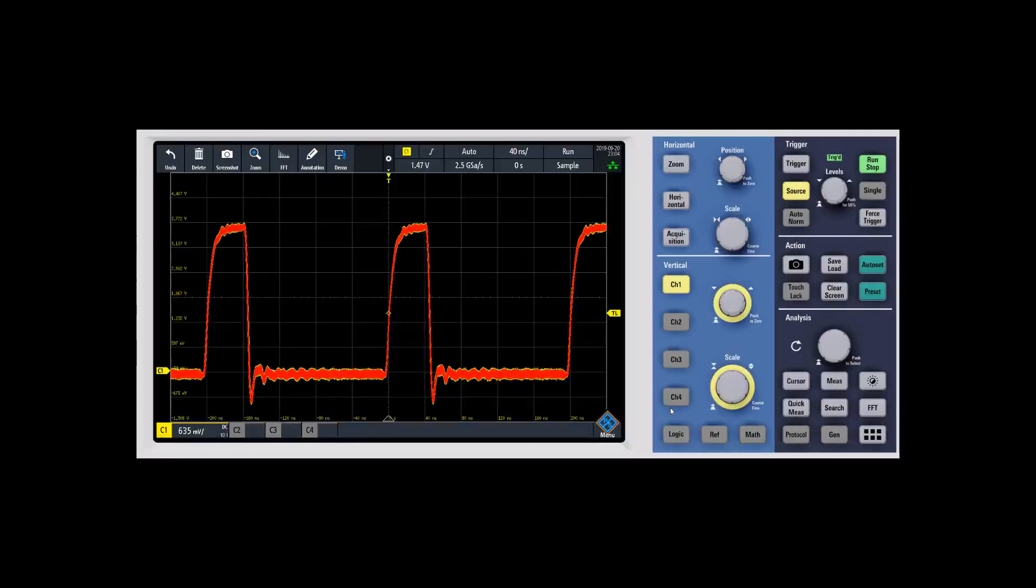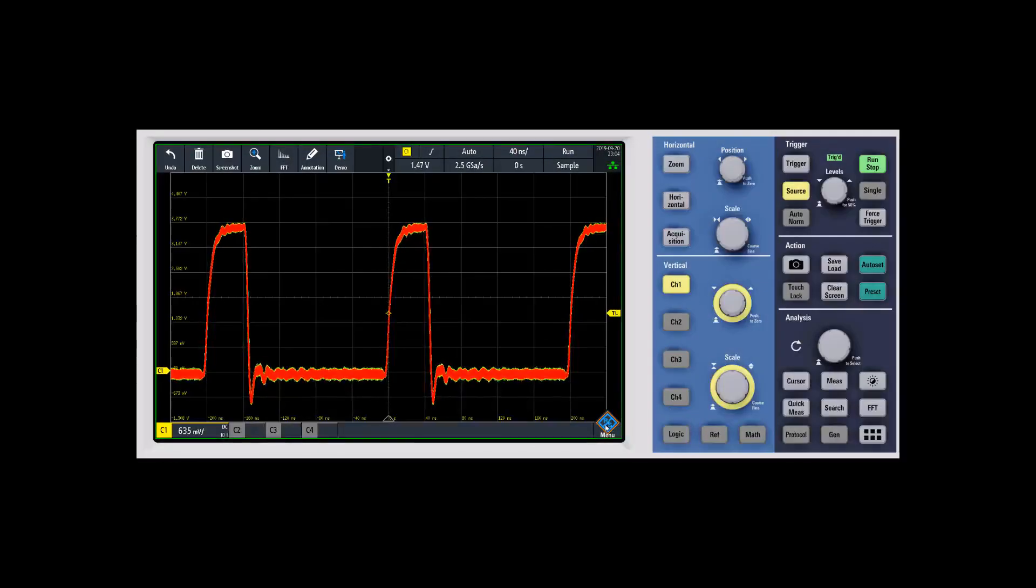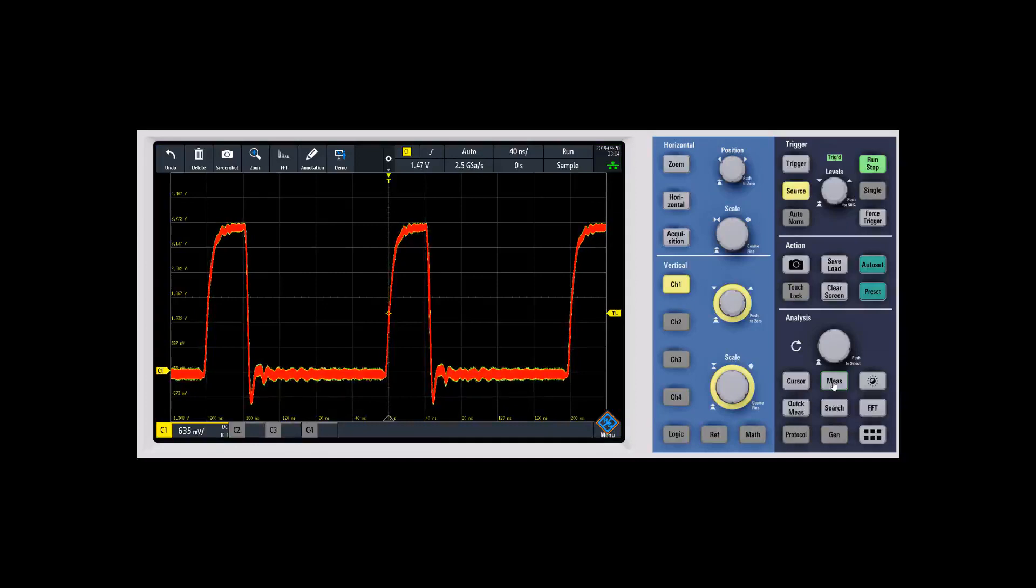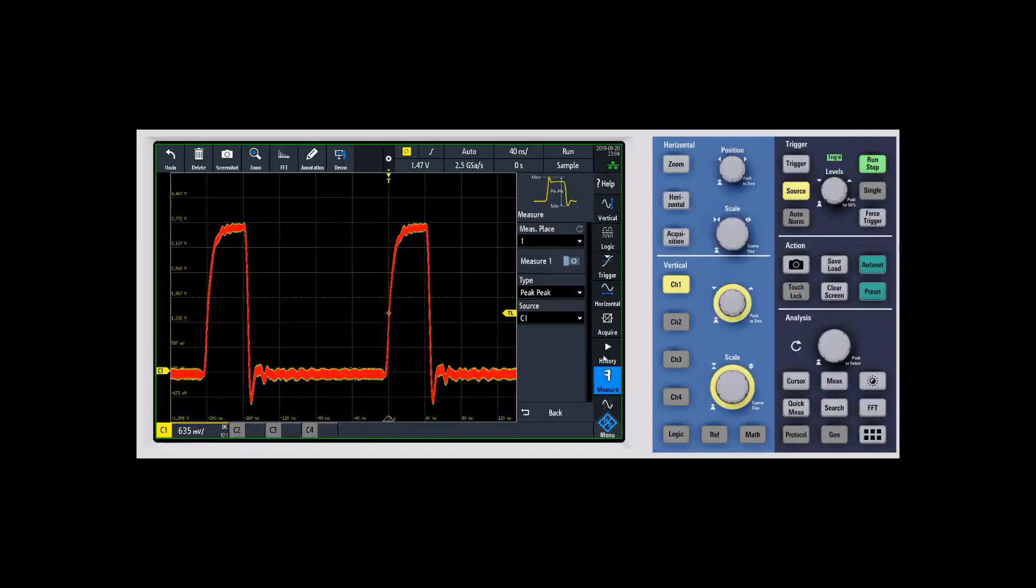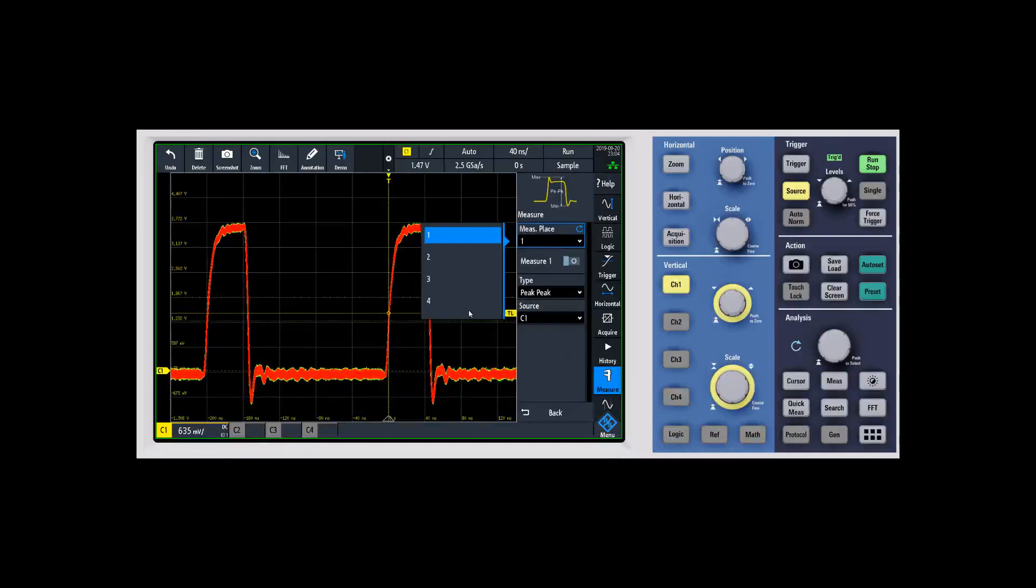In this video we're going to talk about measurements. You can get to the measurements through the menu pop-up here, but there's also a measurements hard key on the front panel. If we start with the measurements hard key, you'll see that it pops into the measure menu. You can have up to four measurements running at one time on the RTB 2000.